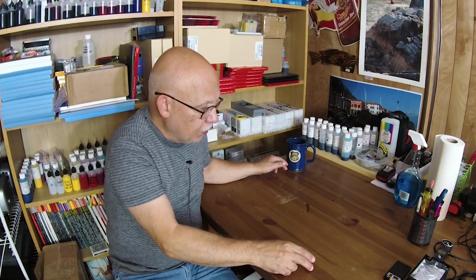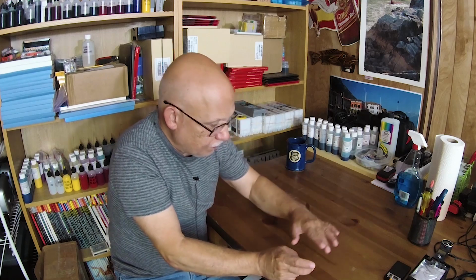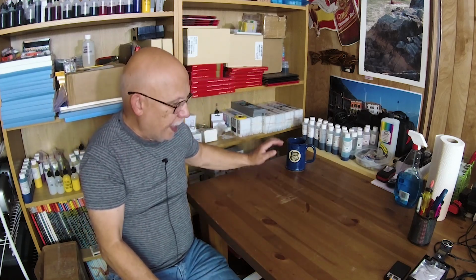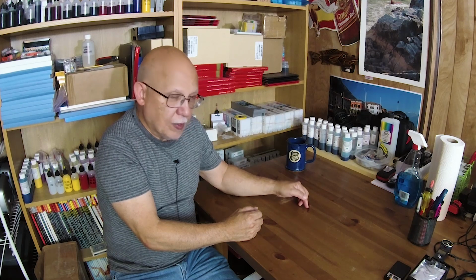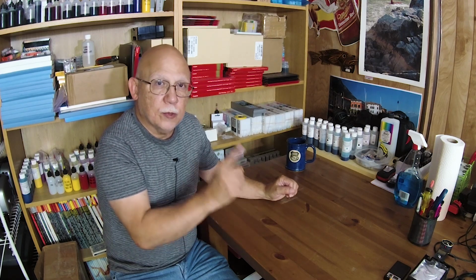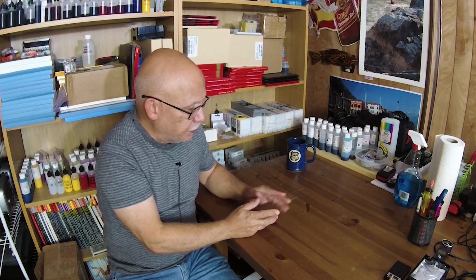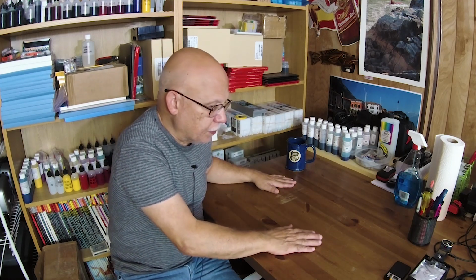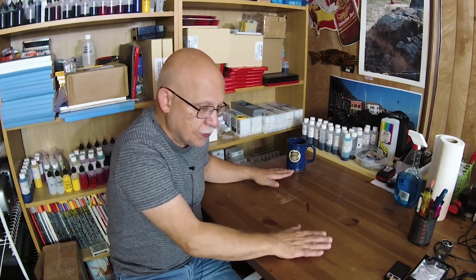Somebody also placed 4 little foam rubber pads under the 4 rubber legs, and that triggered an error. Apparently the sensor couldn't touch the table, so it kept triggering off-level errors. What he did was place the same pad right where the sensor lies, and that fixed the problem. But I'd rather set it up on a flat bench like this, and from that point on, this is where it's going to live.